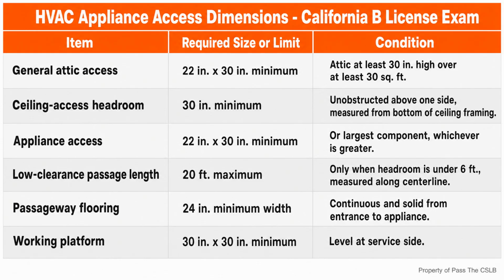At the appliance, the route must end at the correct place. A level working platform at least 30 inches deep and 30 inches wide is required in front of the service side of the appliance. The service side is not whichever side happens to face the catwalk. It is the side where the controls, access panels, filters, burners, blower components, or other service points must be reached. The equipment layout and the platform layout have to agree. A beautiful platform behind a solid cabinet wall does not provide service clearance.